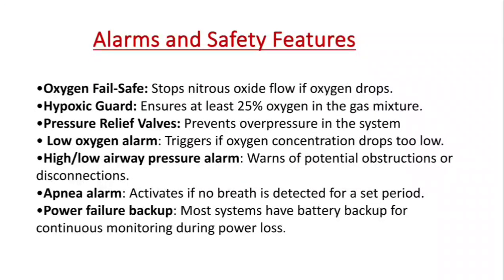Now let's have a look at the safety features. Oxygen fail-safe: what if the oxygen pressure drops? Then the machine automatically cuts off the nitrous oxide to avoid suffocation. Then we have the hypoxic guard. This ensures that the gas mixture always contains at least 25% oxygen and no dangerous gas combinations are allowed. Then pressure relief valves prevent the system from building up too much pressure, which could damage the patient's lungs.